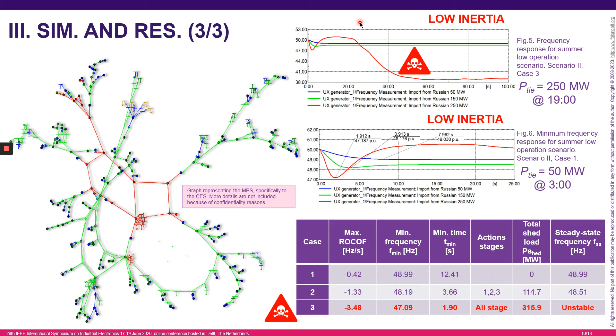Well, it's time to close this presentation with a few conclusions. We are very proud of this scientific paper because we evaluate and assess the under-frequency load shedding scheme in Mongolia. The scheme is the classical traditional under-frequency load shedding that is decentralized, with local measurements and decisions, okay? We identified that the summer represents the low inertia scenario, and when the importation from Russia to Mongolia is 250 megawatts, we can have some problems, okay? We are working toward solving those problems.